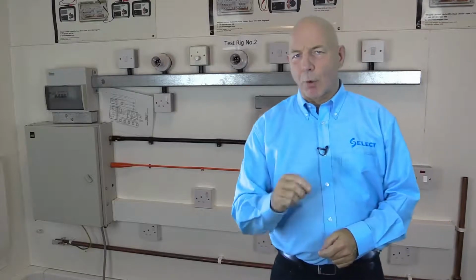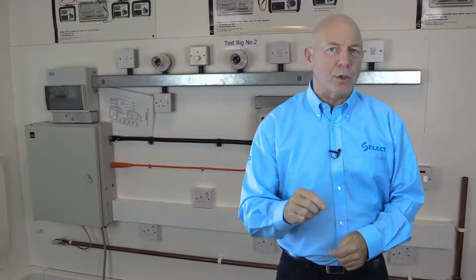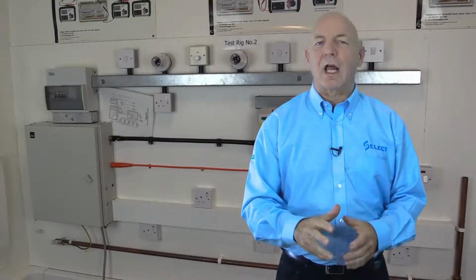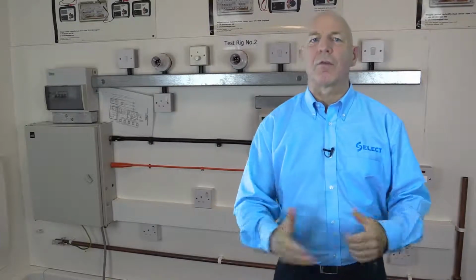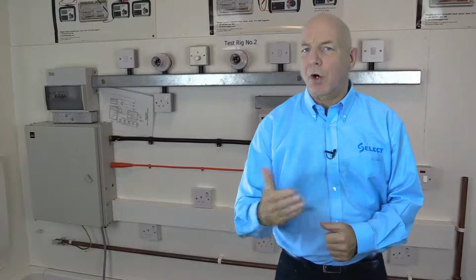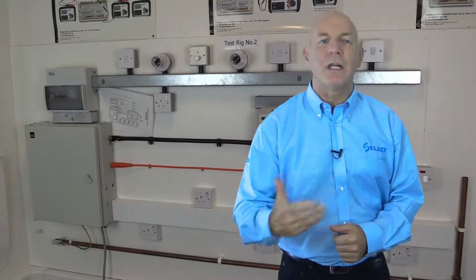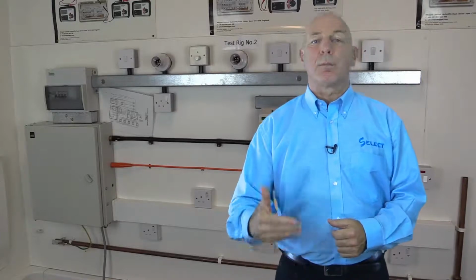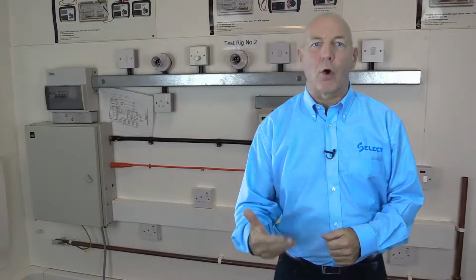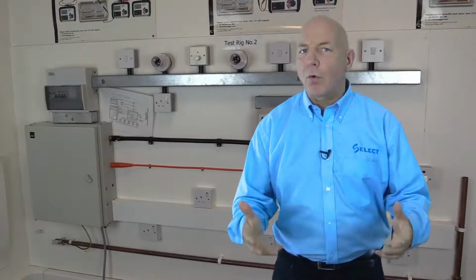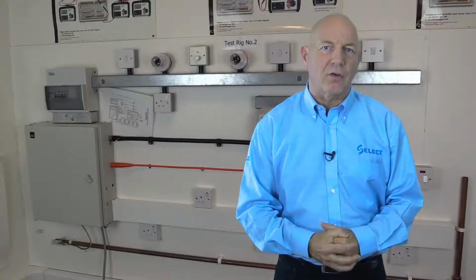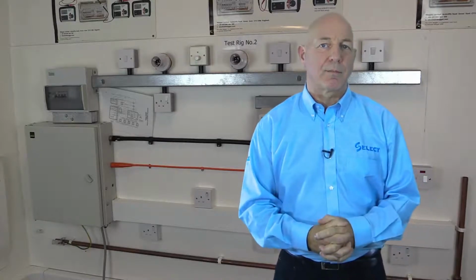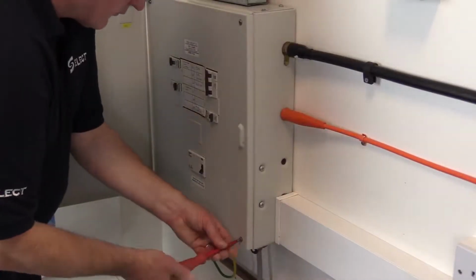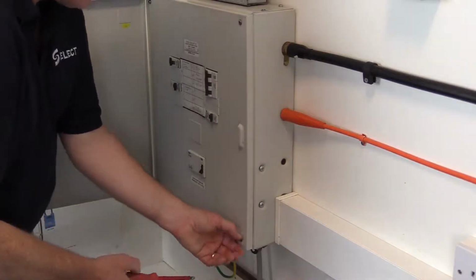Regulation 610.2 requires that information should be given to the inspector, such as the general characteristics of the supply, for example the type of earthing system, nominal voltage, nature of the current and frequency, prospective short-circuit current at the origin of the installation, earth fault loop impedance of that part of the system external to the installation. So let's now take a look at the test rig that we're going to use for this demonstration.